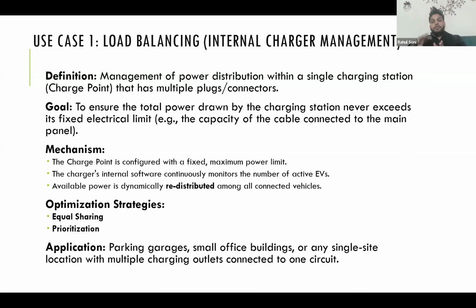The goal is to ensure the total power drawn by the EV charging never exceeds its fixed electrical limit. So if the load sanctioned to that site is 100 kilowatts, and you have 40 chargers of 10 kilowatts each, that's a requirement of 400 kilowatts. Your aim through this use case, using smart charging, is to ensure maximum utilization of that load never exceeds the fixed electrical limit, so you don't get fined or cause damage.